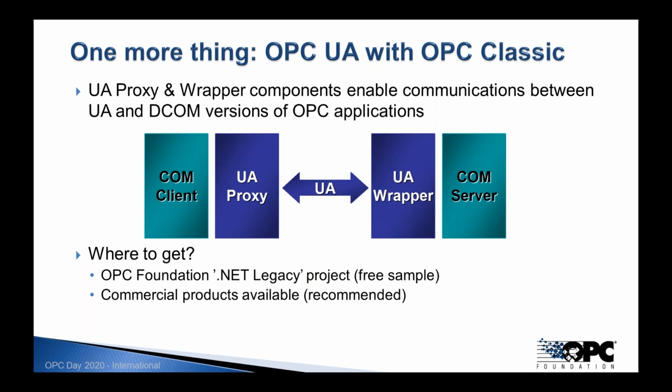They can convert between OPC DA, alarms and events, historical data access, and OPC UA includes all of these, so they can all go into the same channel and provide you, first of all, security. And this is the reason why this kind of tunneling is even recommended. If you have no OPC UA applications on your site, you can start tunneling the classic communication over OPC UA, and then you can be more relaxed, take these communications through firewalls between the production network and the office network, for example.